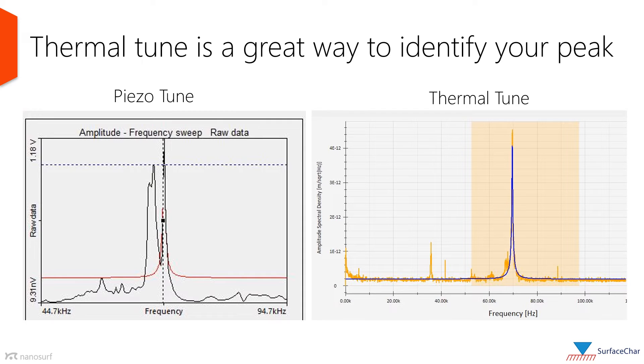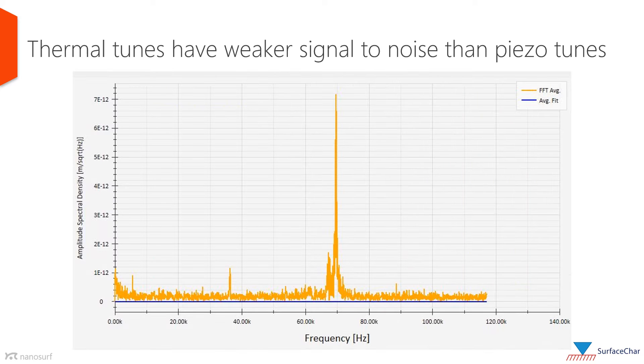Since the cantilever vibrates on its own thanks to the energy imparted to it by molecules moving at room temperature, a thermal tune can be performed, which can also be used to identify the resonance frequency of the cantilever. Typically, thermal tunes have a weaker signal-to-noise ratio than the piezo tunes.